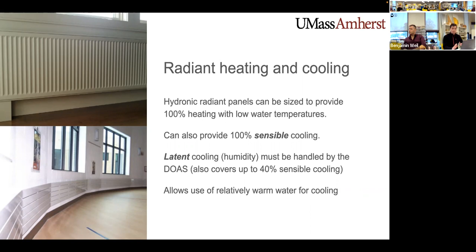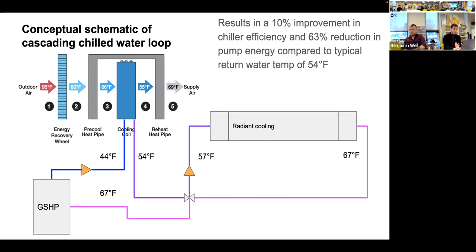This image is a conceptual schematic of a cascading chilled water loop. The way this works is that water enters the dedicated outdoor air system's cooling coil at 44 degrees and leaves at 54 degrees. Then a three-way mixing valve mixes the return chilled water to supply radiant panels with 57-degree water so that the average water temperature is 62 degrees, which is well above dew point, and the final return temperature is 67 degrees. The result of this process is a 10% improvement in chiller efficiency and a 63% reduction in pump energy compared to a typical return water temperature of 54 degrees.